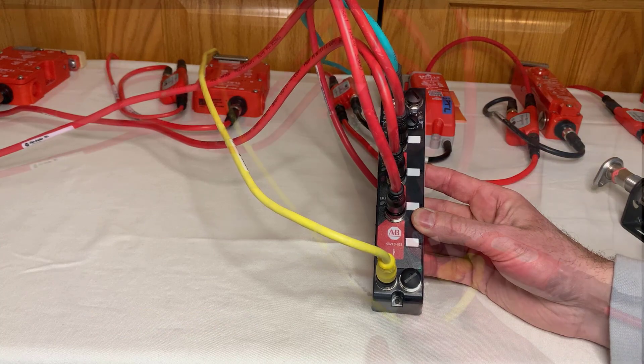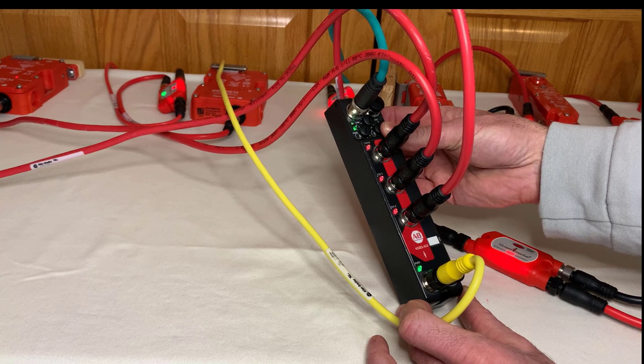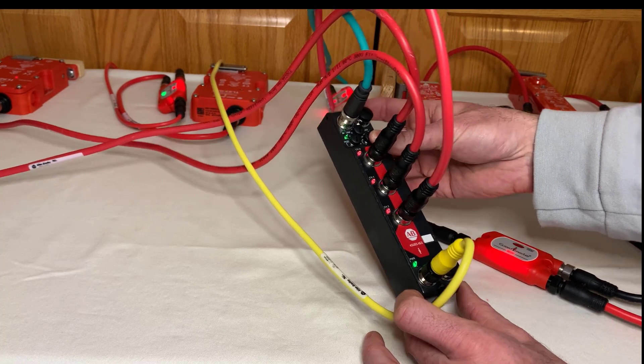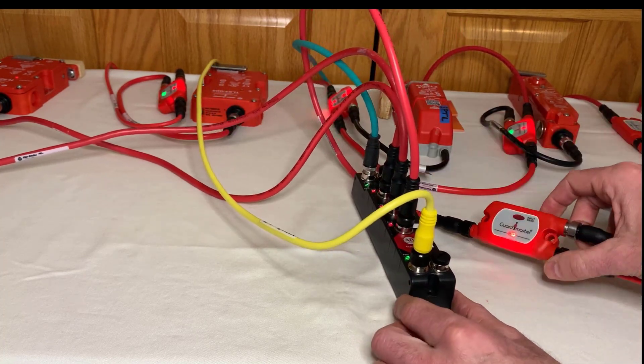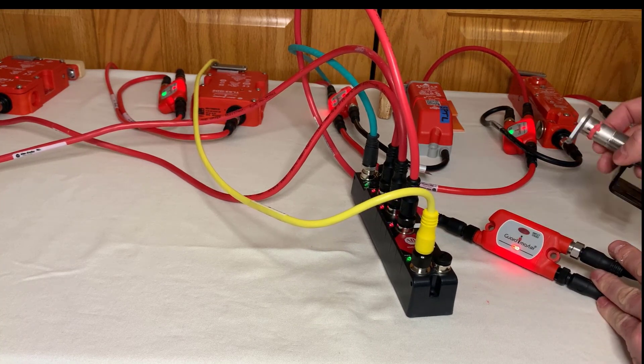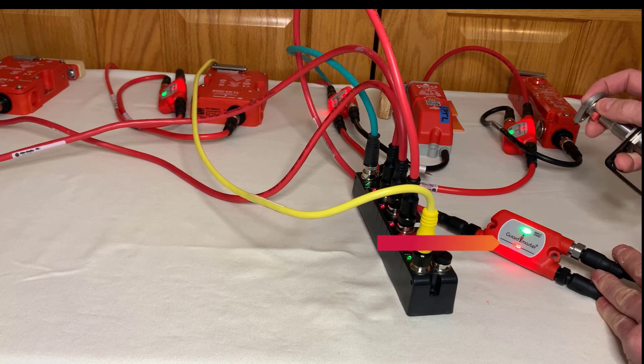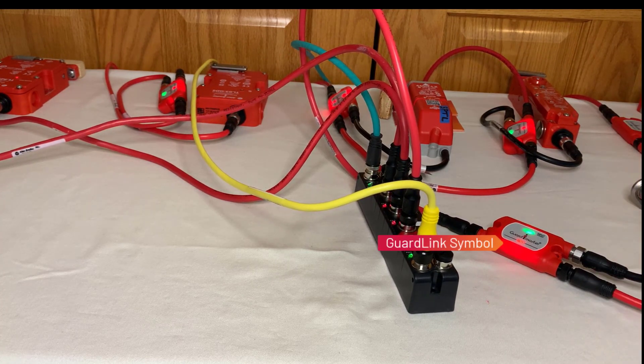When the power is applied to the GuardLink interface, the GuardLink input channels will flash red until correctly configured and connected to a GuardLogix controller. Even without GuardLogix connected and configured, a preliminary checkout can be made. All GuardLink taps should show an illuminated red GuardLink symbol.